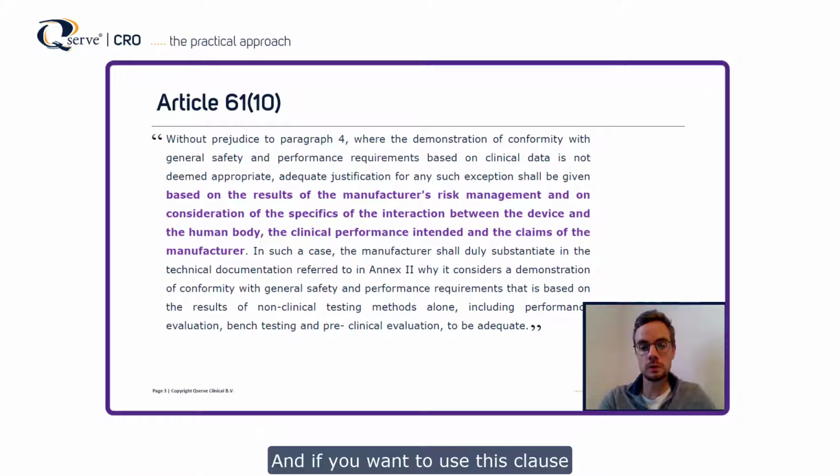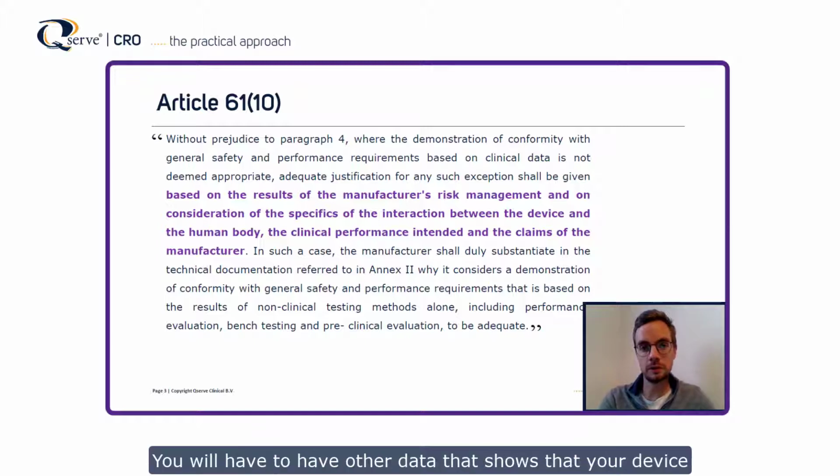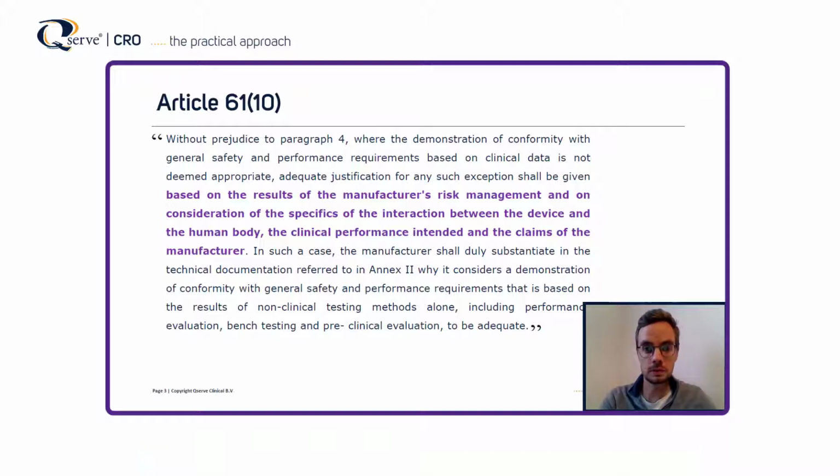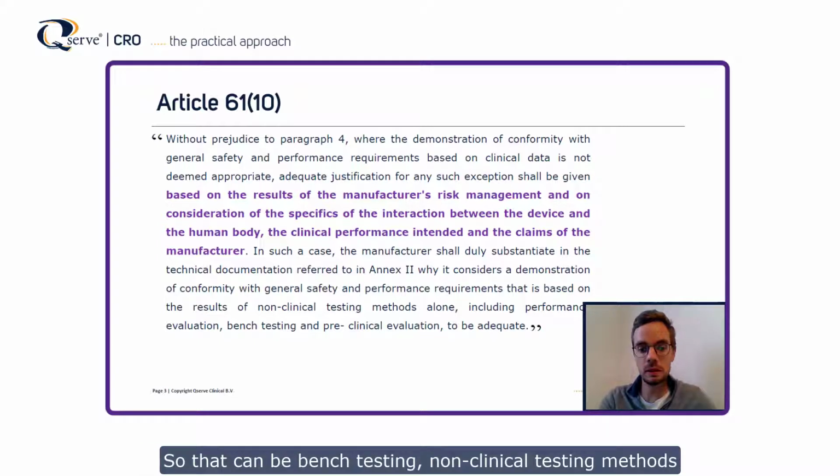And if you want to use this clause, you will have to have other data that shows that your device conforms to the general safety and performance requirements. So that can be bench testing, non-clinical testing methods, preclinical evaluation, and performance evaluation.